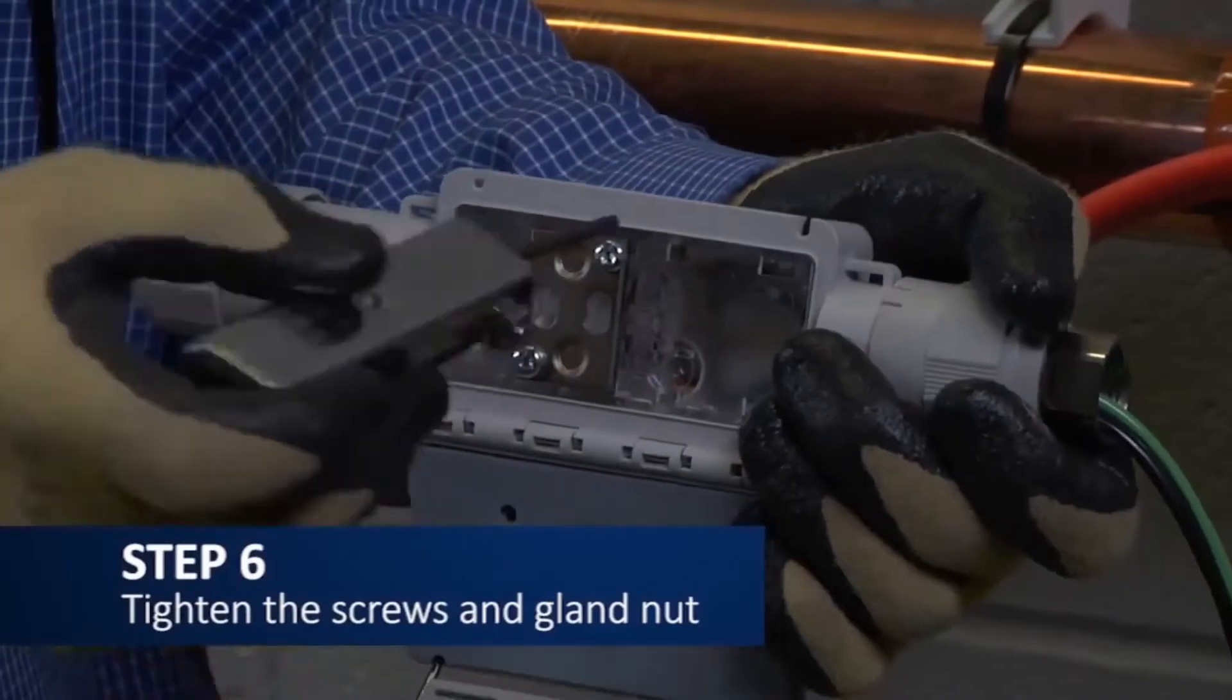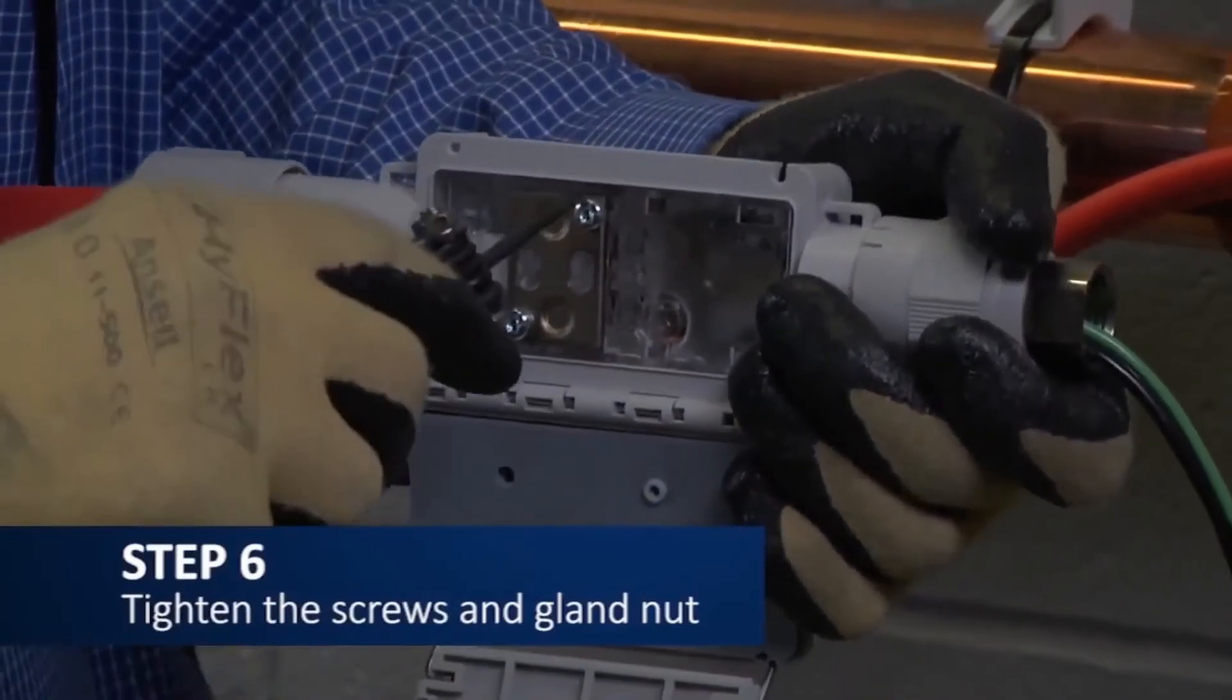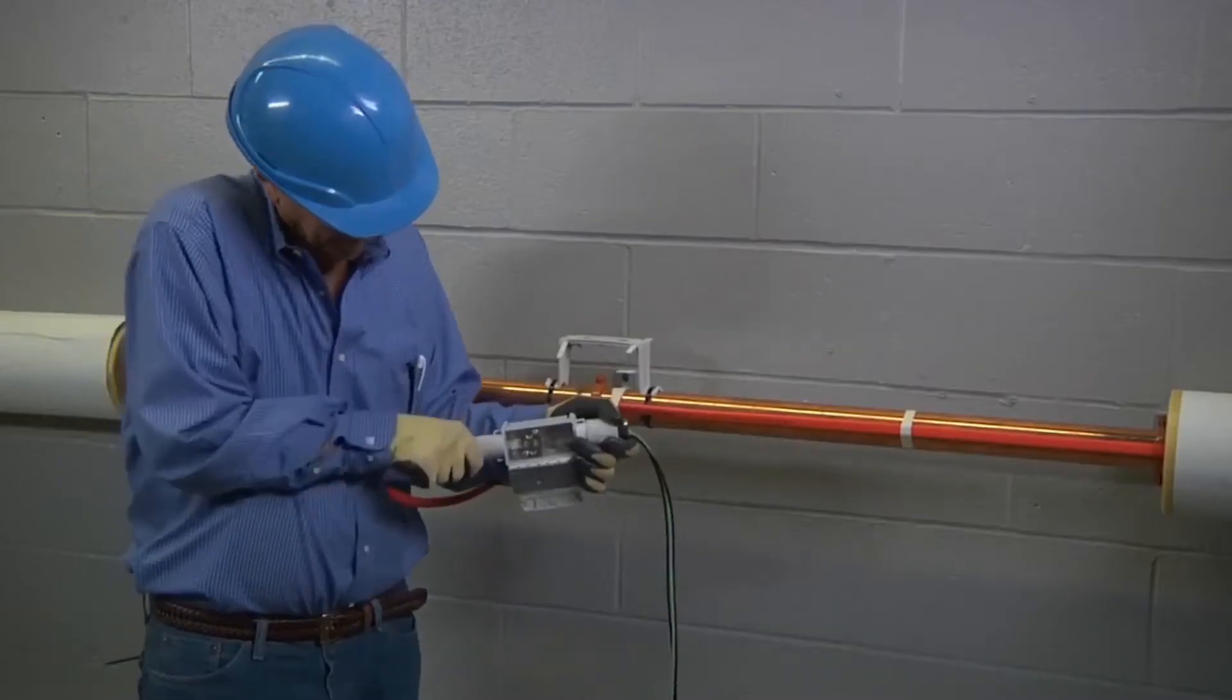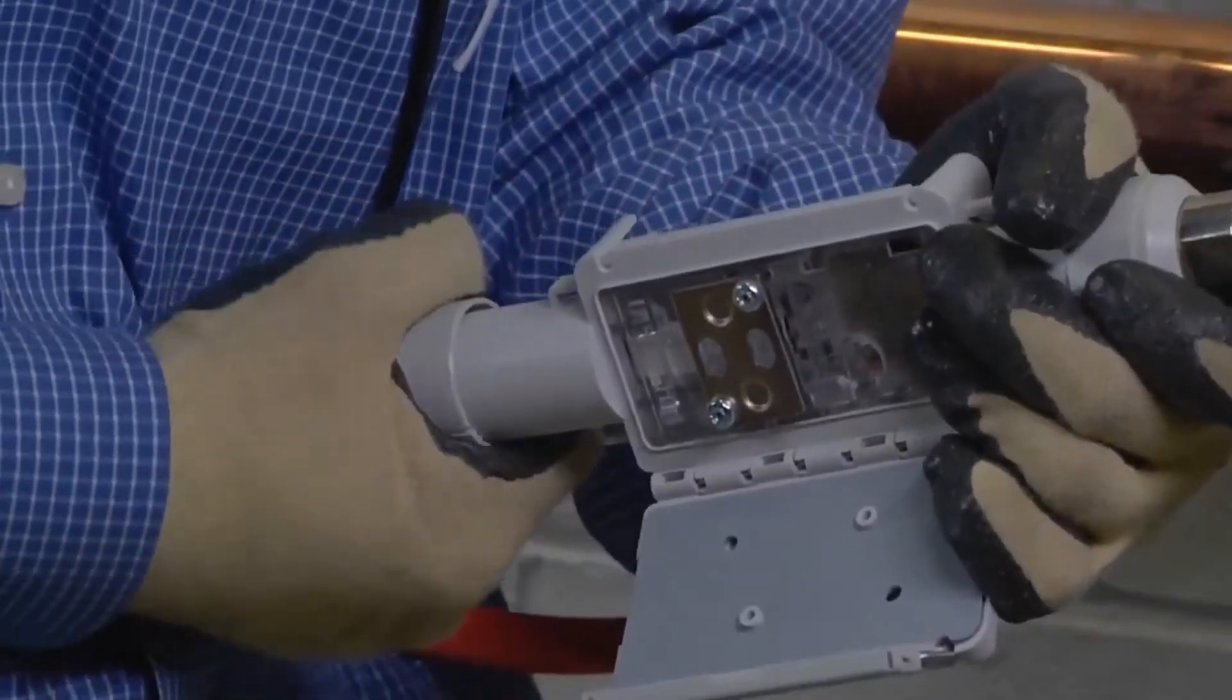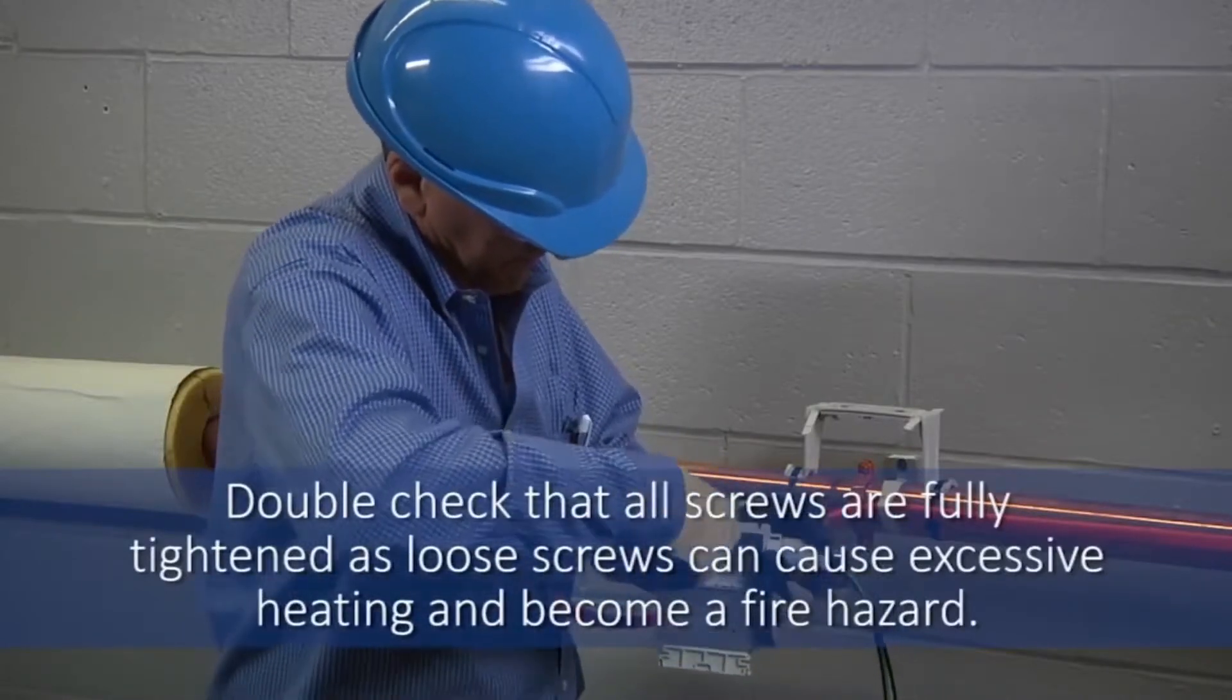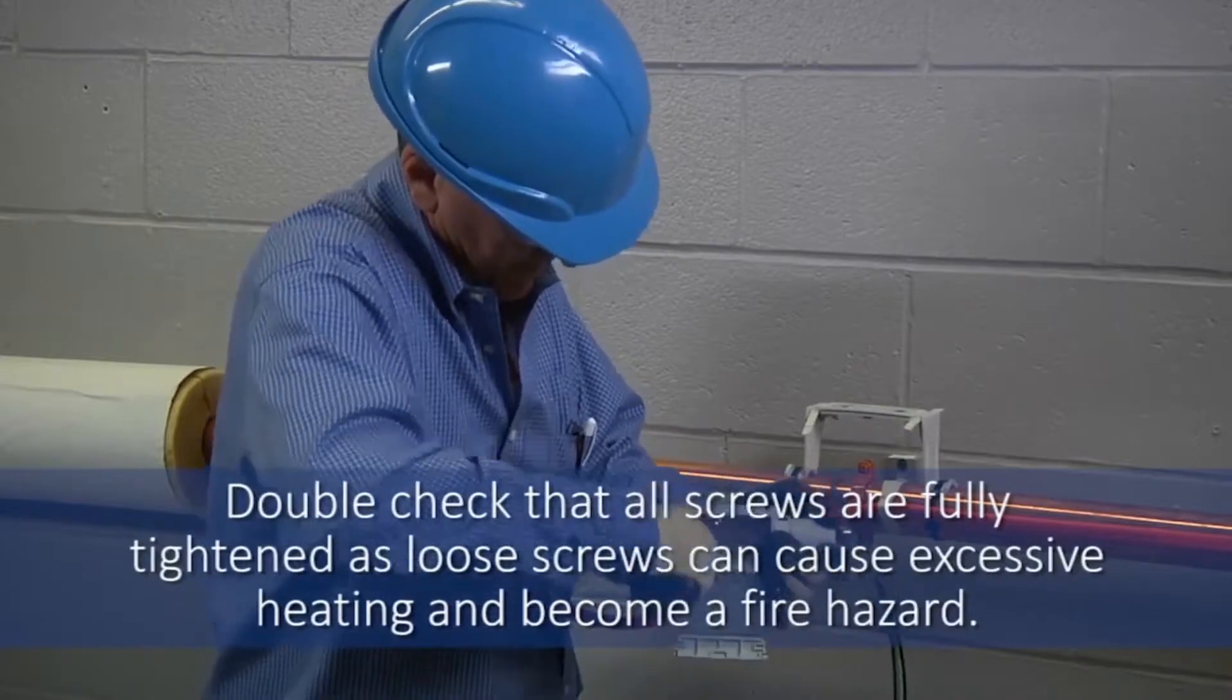Continue by tightening the Torx head connection screws with the Torx screwdriver, alternating between them as they are being tightened. Also, tighten the gland nut on the heating cable entry until the rubber grommet is compressed. Double-check that all screws are fully tightened, as loose screws can cause excessive heating and become a fire hazard.